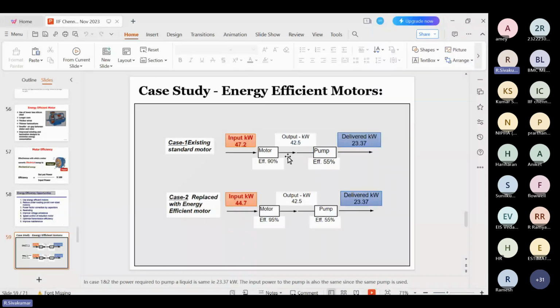At this time, the input power drawn from the grid, from the mains, is 47.2 kilowatt. The same motor was replaced with an energy efficient motor, from 90% to 95%. What happened? The delivered output is the same 23.37 kilowatt, and the same pump efficiency of 55%. Only the motor efficiency changed from 90 to 95%, so the input power drawn is reduced from 47.2 to 44.7. Suppose this pump is running, for example, as a coil cooling motor in the furnace.